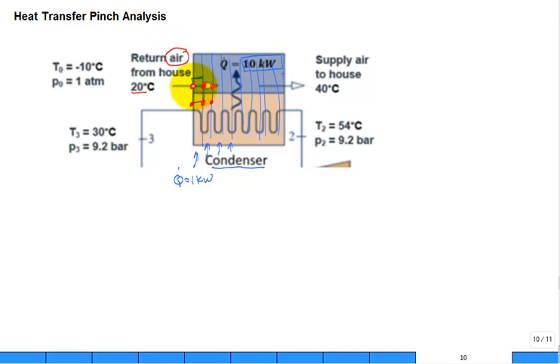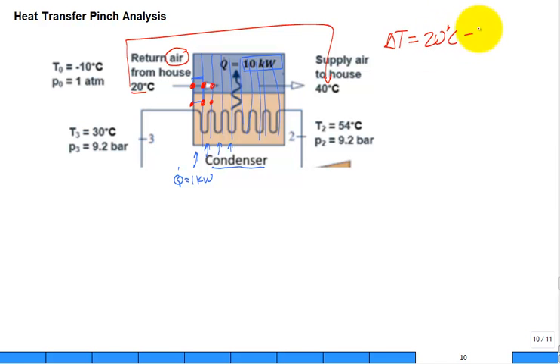Then I do an energy balance check. The cold comes in at 20 and the hot leaves at 30 — can I predict the temperature at intermediate points for the cold as well as the hot? You can do that and just continue the process. For the air, this is easy: if you bin it up and the delta T from inlet to outlet is 20 degrees C — that's 40 minus 20 — and you have 10 bins, the delta T per bin would be 2 degrees.